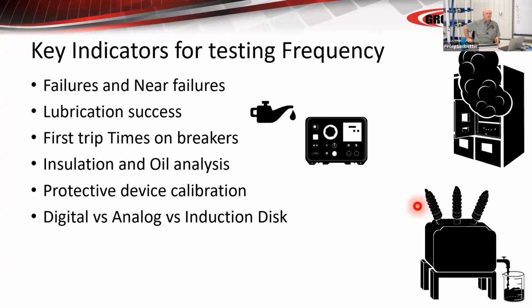You go beyond 5 years, say to 7, and we start to see 20, 22, 23% of the breakers running at a speed and velocity, or having an issue with lubrication or a mechanical issue or a timing or calibration issue that might have caused a failure. Then the breaker would not have performed properly if it was asked to do so. First trip times are your best indicator of that.